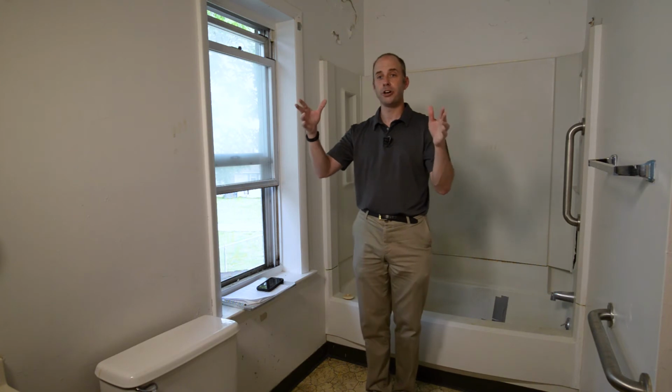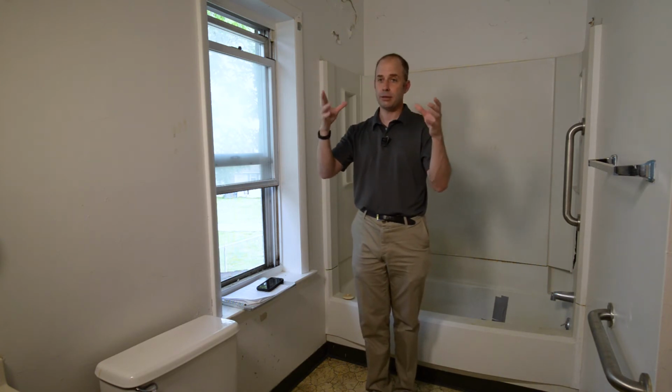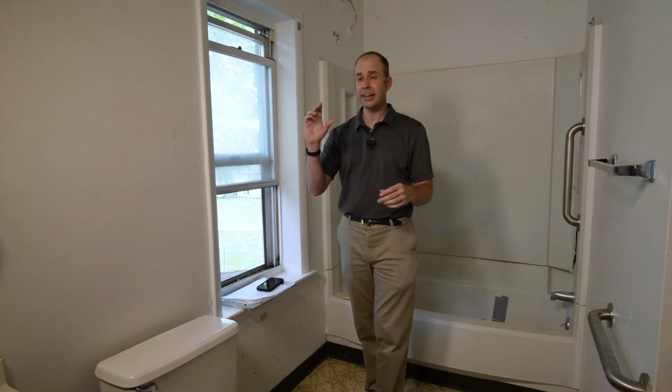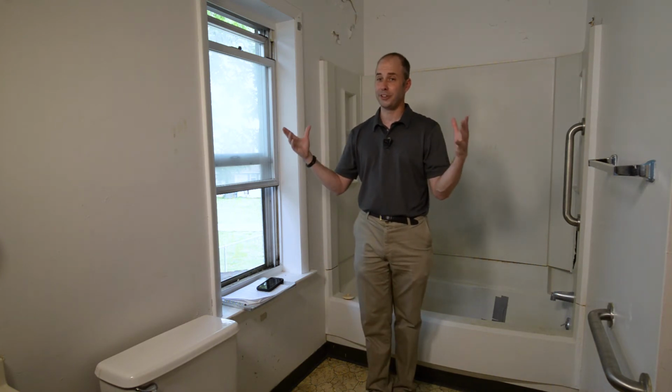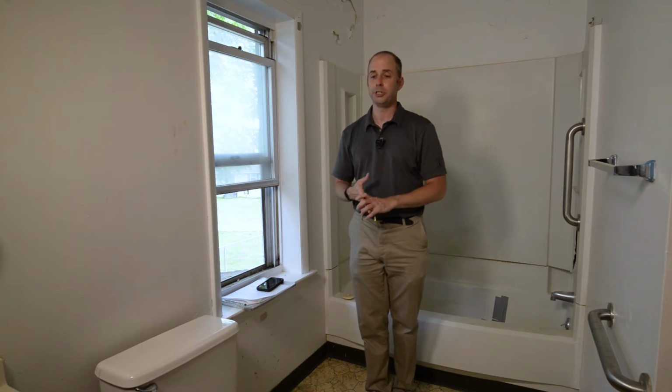When we're looking at the light, it needs to be secured into the location, and if it's designed to have a globe, the globe is to be in place, and then also we need the light bulbs in place for an inspection. That is so that we can ensure that the equipment is actually functioning as it's supposed to. So the light bulbs do need to be in place.